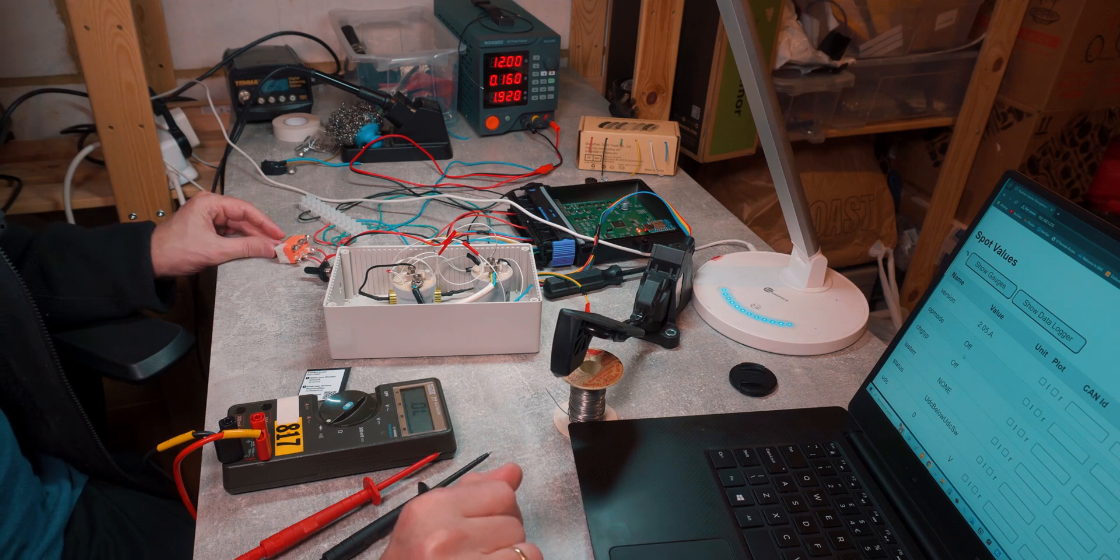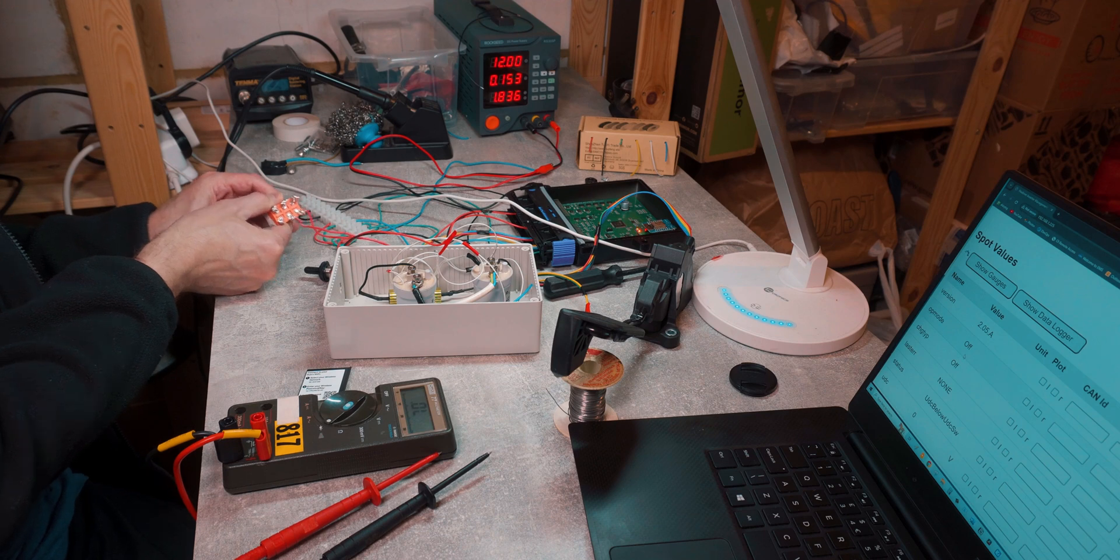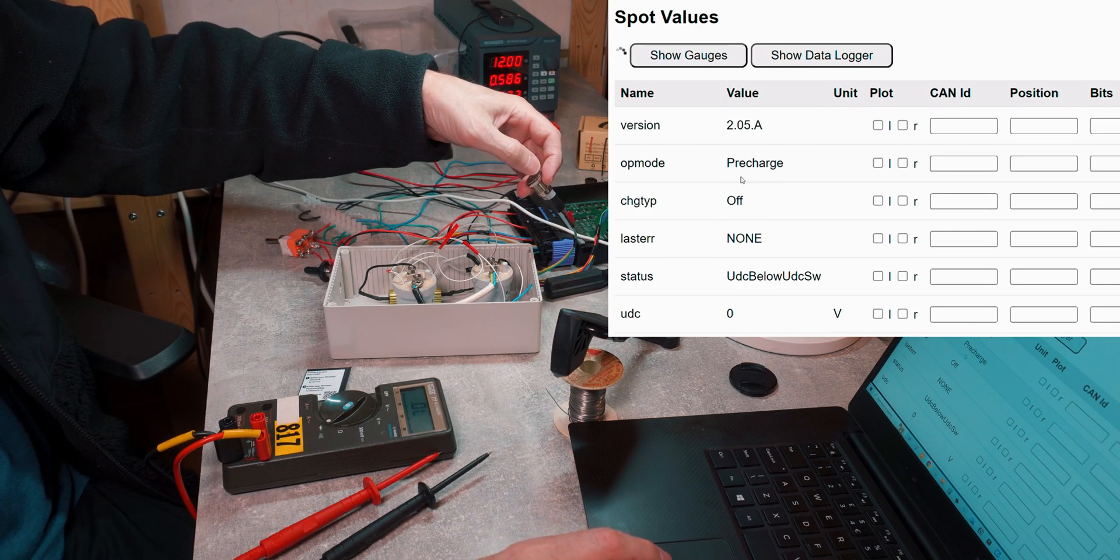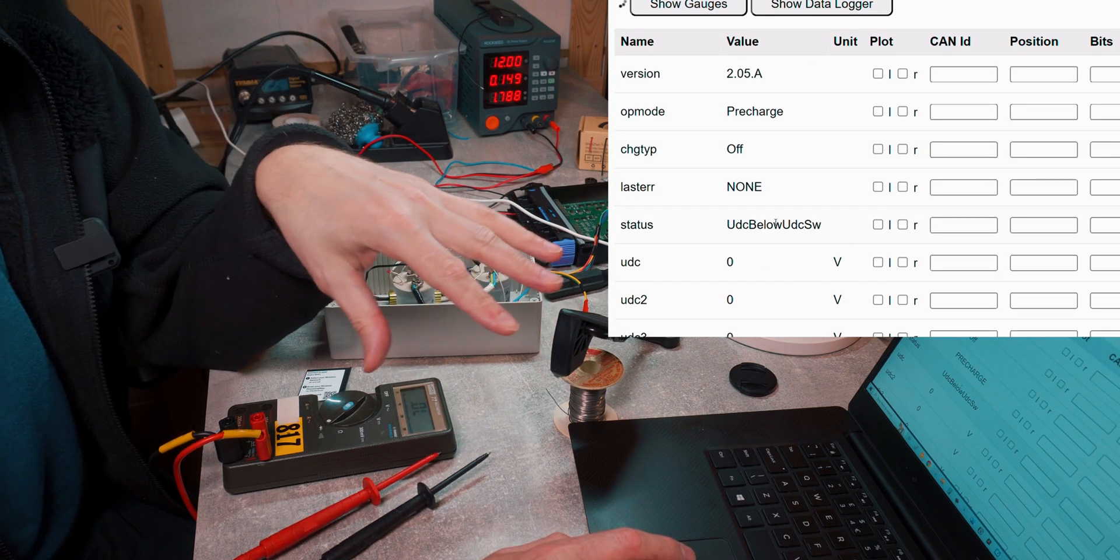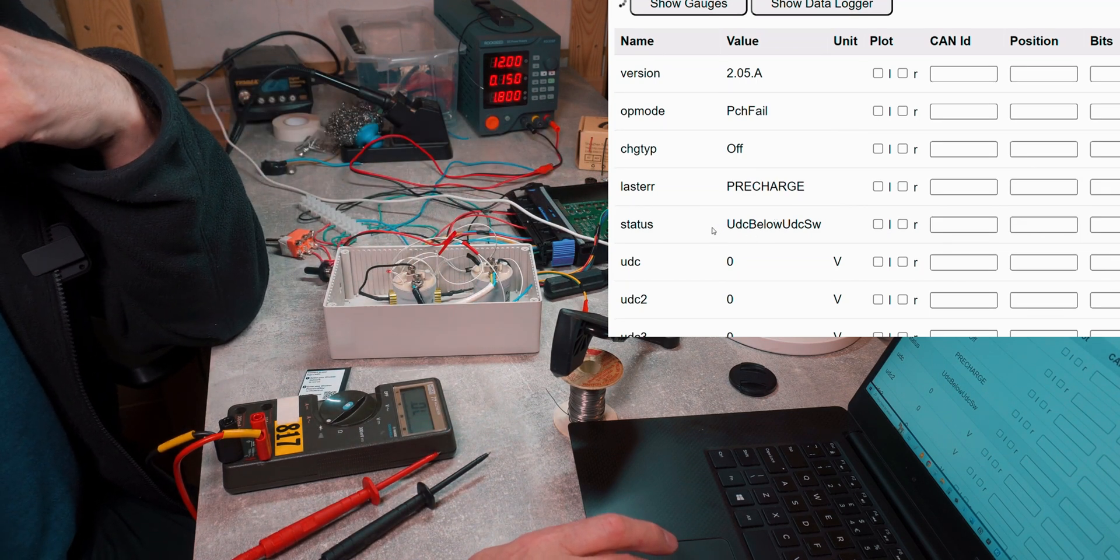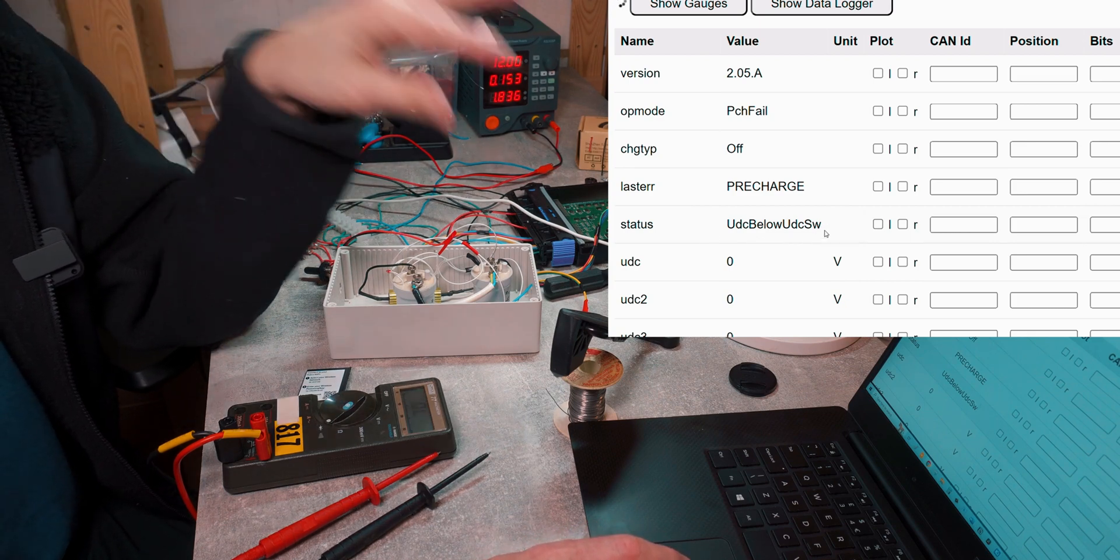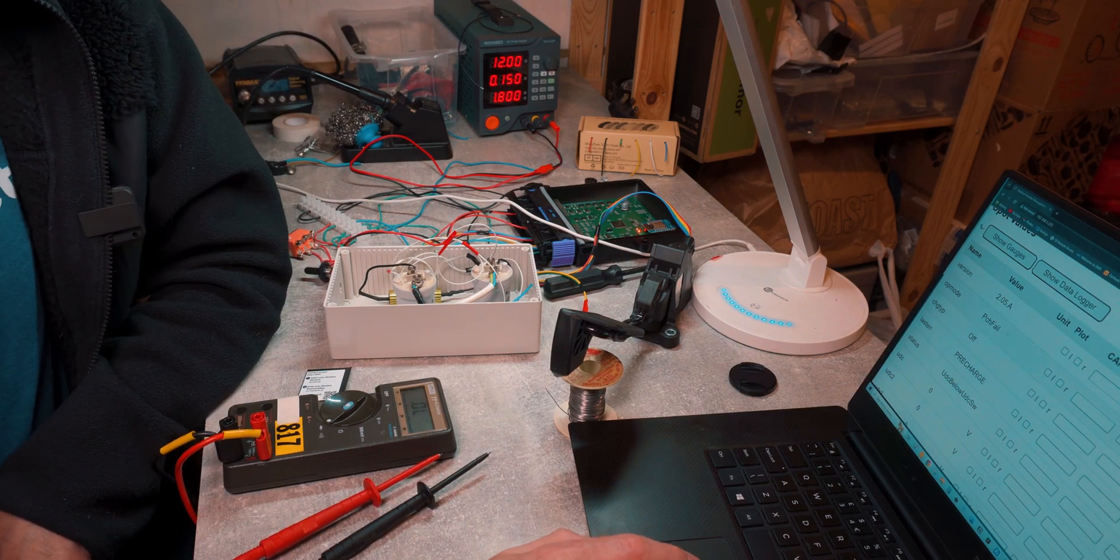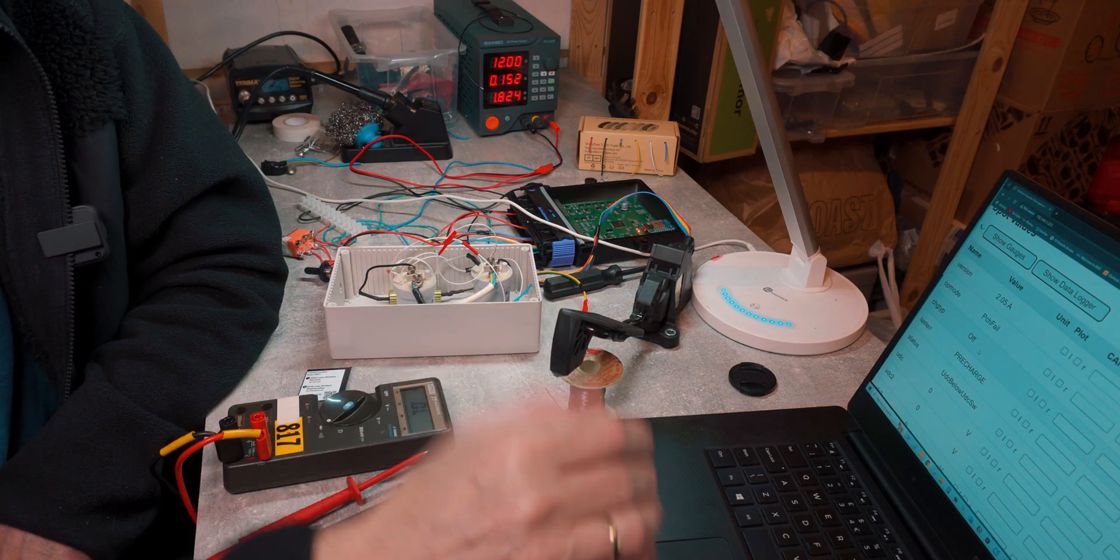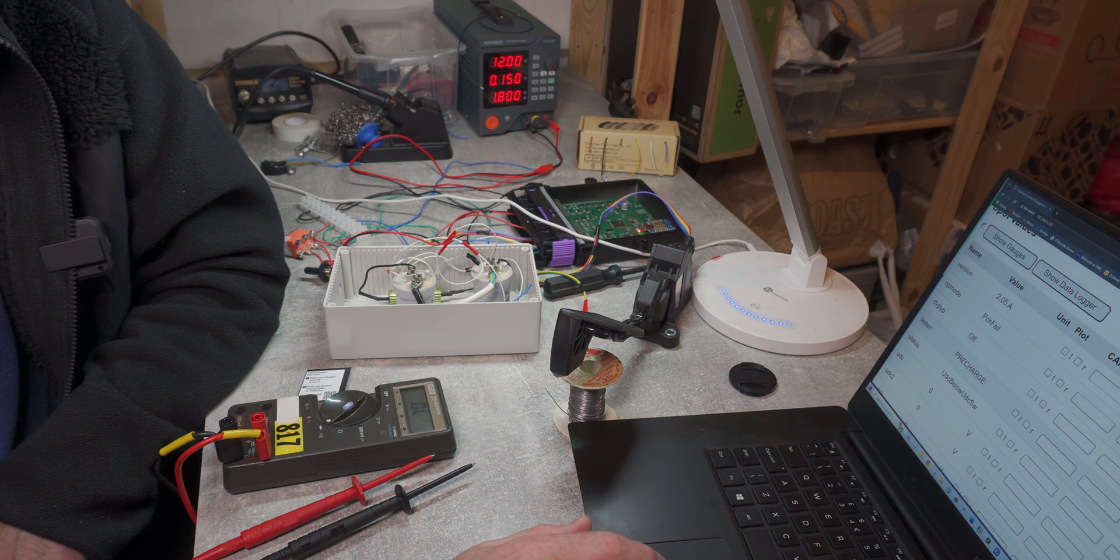So here we can see it goes off the run mode, and now if I go back into ignition mode and press start button, we can see pre-charge, but the system doesn't go into the run mode because it has an error message. Status is UDC below UDC SW. So our UDC SW minimum value is 30 volts and it's never managed to reach that value. So for this reason we have pre-charge fail and last error message is pre-charge.